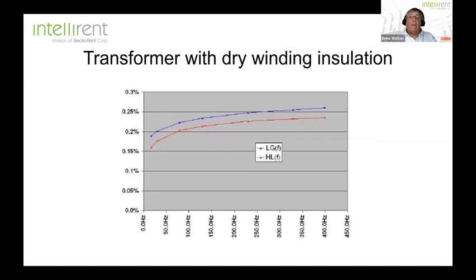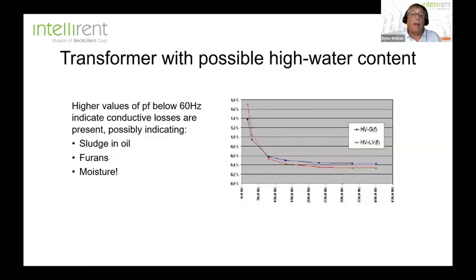So if we look at an actual test here, this would be a measurement of a transformer with a dry winding insulation. Okay, and you'll notice that below this 60 hertz value, it's coming in at a lower value. Okay, now, does it matter how much lower? Not really. It's really the angle at which those measurements are coming through that 60 hertz measurement. Okay, now, if we have higher values of power factor, that would indicate conductive losses. But again, this could be sludge in the oil, it could be furans, but it could also be moisture.